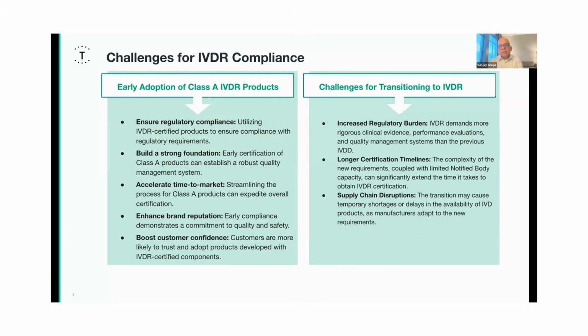So, of course, challenges abound, and there is an increased regulatory burden. It takes longer. We need a lot of clinical evidence for Class A products as well, and also longer certification times. There's also a potential for delays in manufacturing these, because it takes longer. You have much more rigorous quality control measures. And so the cycle time is much larger in terms of manufacturing these devices, and then also qualifying them for the indication and the intended use that they are approved for. So really, one has to think about these challenges holistically. These are basics, I'm talking about Class A products. Then you go for Class B, C and D products, and as they are getting submitted, it's definitely better to partner with companies who already have Class A approved products. It's definitely a benefit because it reduces the cycle time and the burden.